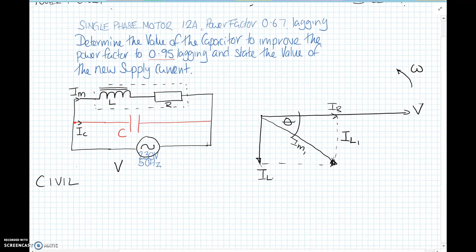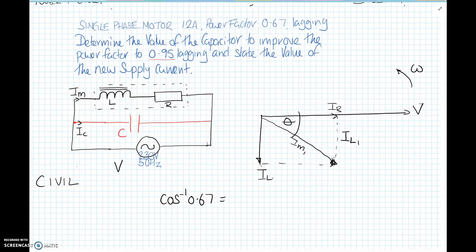So let's put some figures in then. Before we start, we know that the power factor is given as 0.67. So to change that into an angle, we need to inverse cosine the factor to get the angle. Make sure your calculator's in degrees and not radians. So we've got inverse cosine of 0.67, which gives us 47.93 degrees. So that's what this angle's going to be.